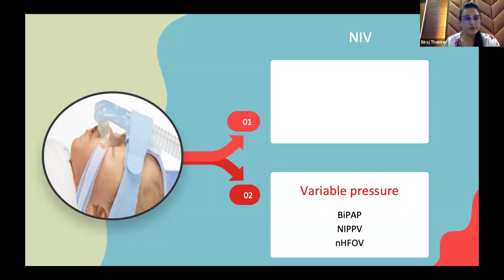So what is BiPAP? It is kind of a CPAP where there is one level of the PEEP, and on top of that there is a second level of the PEEP. So there are two levels of the PEEP. Here we can see that the second level of PEEP is also being set, but the delta P here is very less. Like, if you have set the PEEP of 5, then the second level would be somewhere around 8 to 10. So the delta P set here is less.